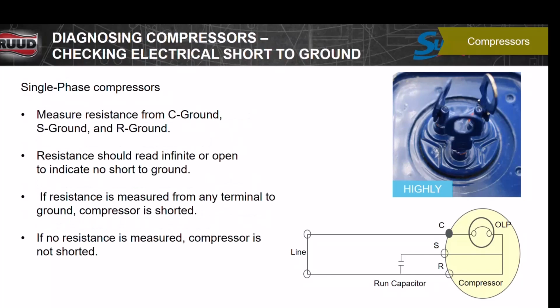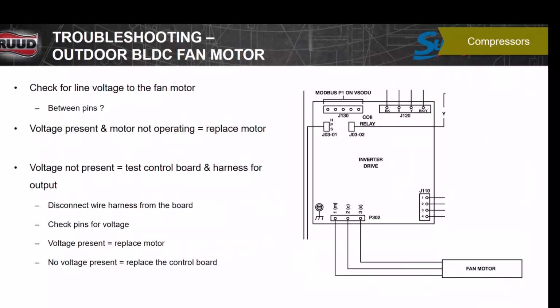You should read what you would normally read on your ohms readings on a compressor here. On a 3-phase compressor, you read equal on all 3 legs. Here, you're going to read like you do on a regular capacitor-driven compressor motor. On the outdoor fan, the other question hadn't come up yet, but I'm going to wait to the end to see if it does. But the outdoor fan motor works off the inverter, so even though the contactor's pulled in, the inverter is still controlling that motor.